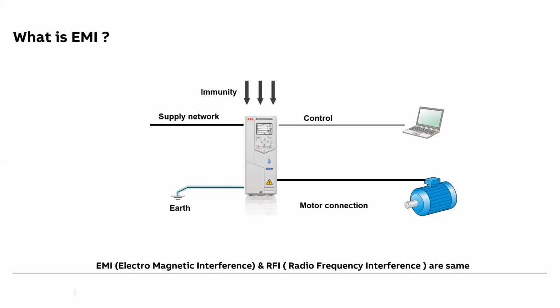Then second is the emission. First it should be immune, and then it should also not emit RFI so that it affects other equipment. Now in the emissions there are basically two types of emissions. One is the conducted emission, and another is the radiated emission. Now this IEC code covers both. If it has an EMC filter, it should have an inbuilt EMC filter, and this EMC filter should restrict both radiated as well as conducted emission.